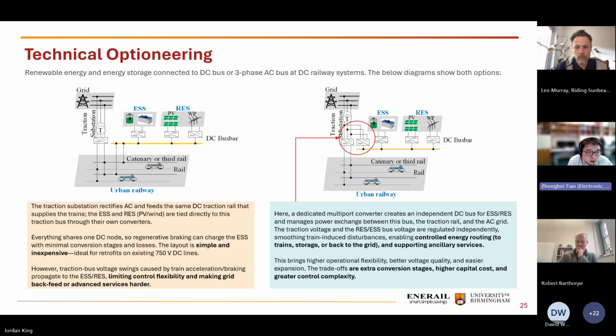There are some challenges with this topology. Because it's simple and inexpensive, we can engage the trains' operation, traction, or regenerative braking with energy storage directly, and the surplus regen power from the trains can be used to charge the DC-connected energy storage directly. When there's higher traction demand, the energy storage from the DC bus can discharge and support this peak demand directly, giving a good enhancement of the railway network's energy efficiency and removing peak demand, increasing railway capacity a little—but it also limits control flexibility.